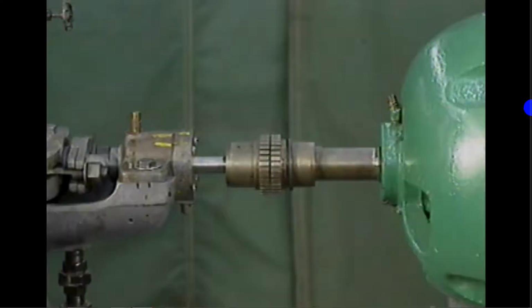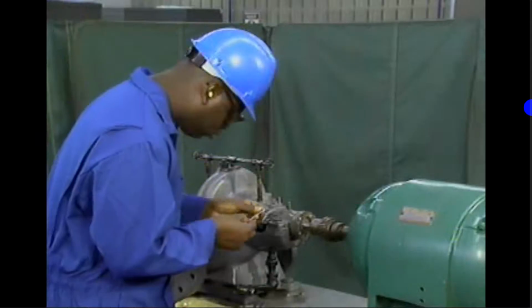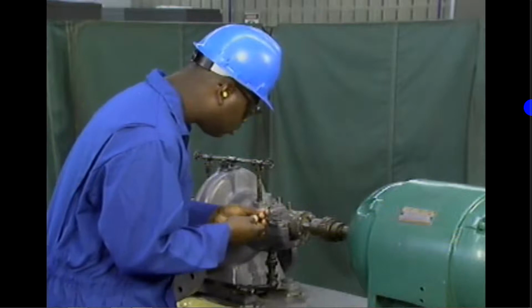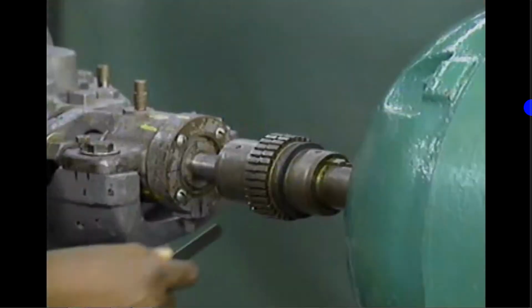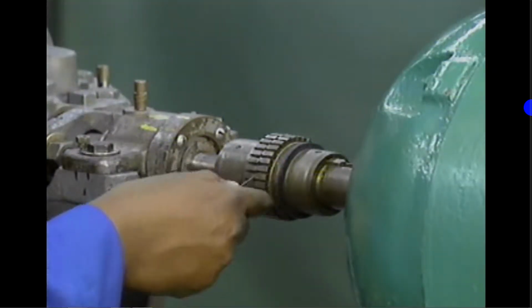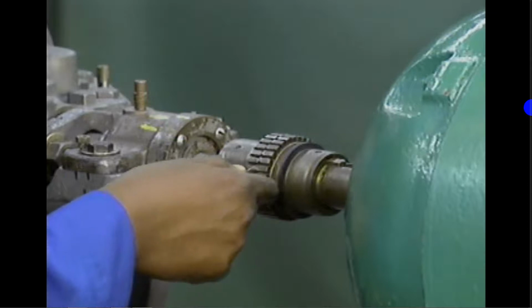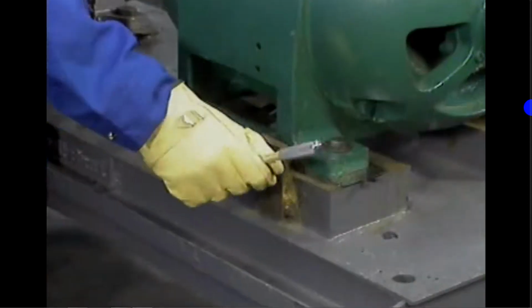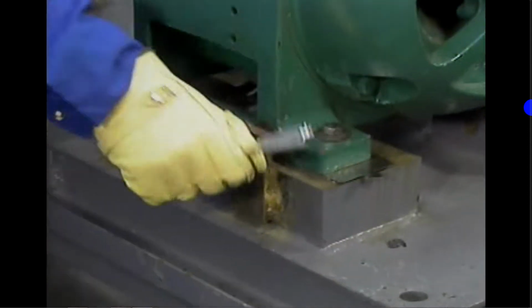Once the shafts of the components involved in an alignment have been positioned at their mechanical and magnetic centers, the coupling face gap can be set to its proper specification. This is done by inserting a feeler gauge the size of the ideal face gap between the coupling hubs and maneuvering the movable component until the proper gap is achieved.